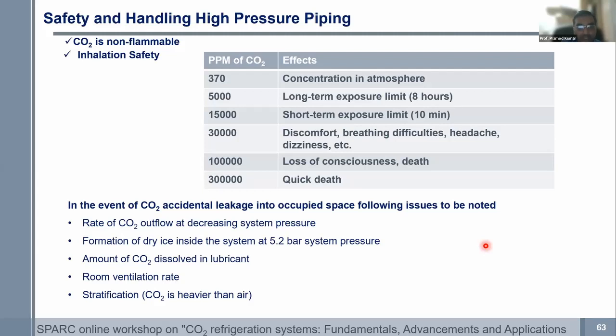It is only that you feel breathlessness because it has displaced air. Okay, so it causes death because of asphyxiation, not because it is poisonous. If you find signs of discomfort, that means there is actually loss of oxygen supply. So this is something you need to be really careful about when you build CO2 systems. You need to have at least a CO2 leak detector installed that will give you an alarm if there is leakage of carbon dioxide. Or you should take potential leakage paths and push them out of the room so that they can be installed in an open environment.